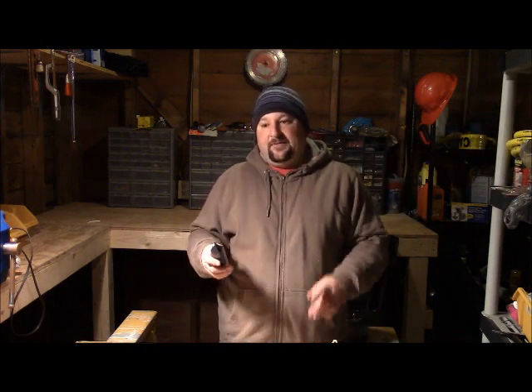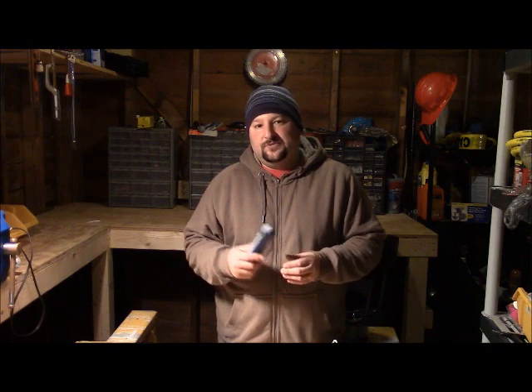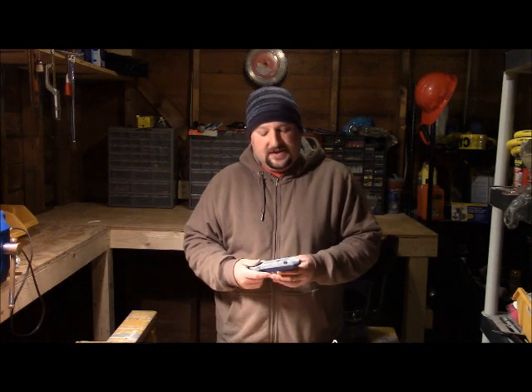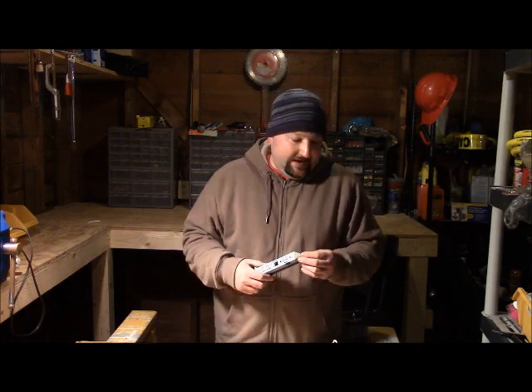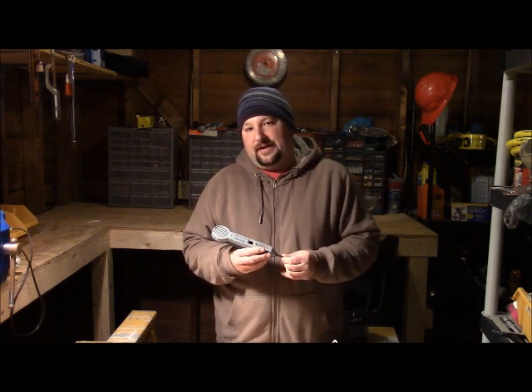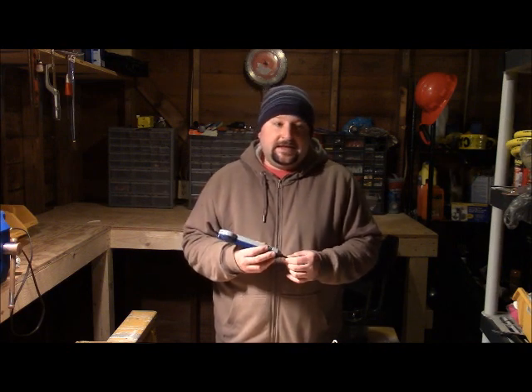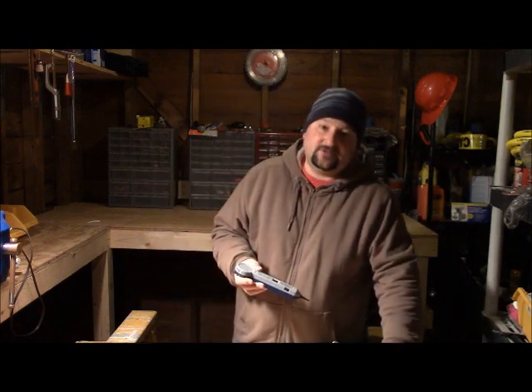What happens is, in an electrical circuit in a house, all your stuff really ties back together at the panel on the common. You have a hot and a common wire. So these are kind of useless for troubleshooting line voltage — 120 or 240 volts. It really is not designed for that. Anybody pushing you to do it that way, I'd shy away from that. At best you'll damage a $70 tool; at worst you might injure yourself or do damage to an electrical circuit.